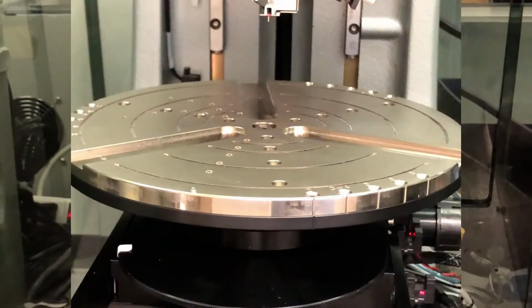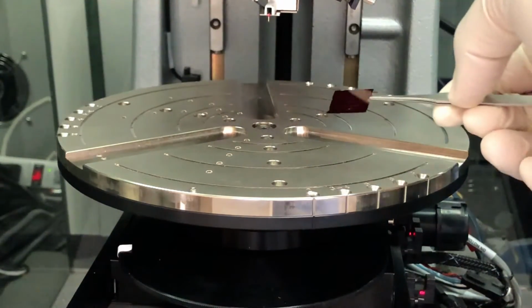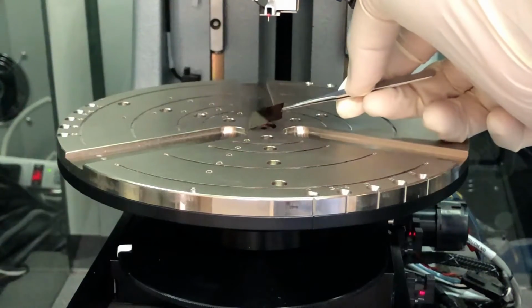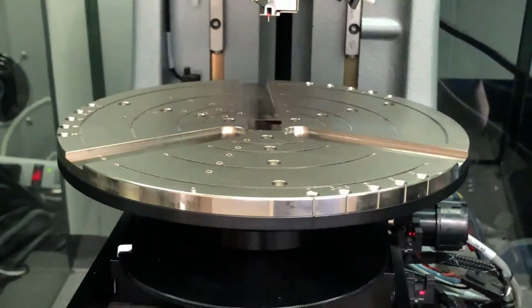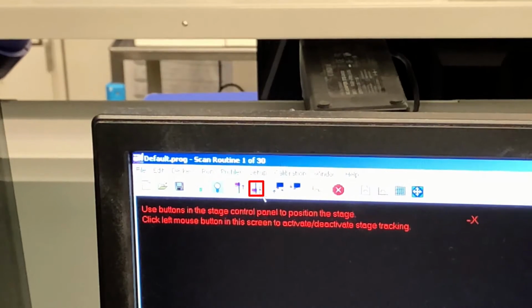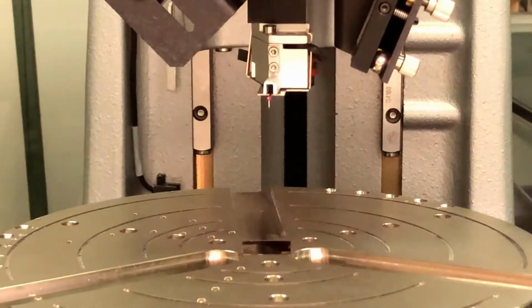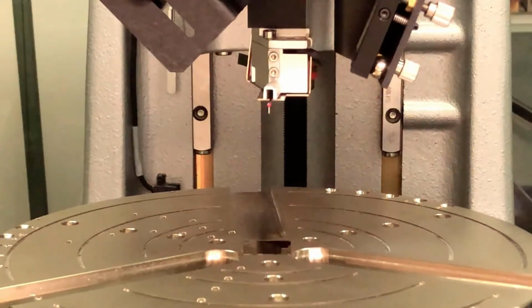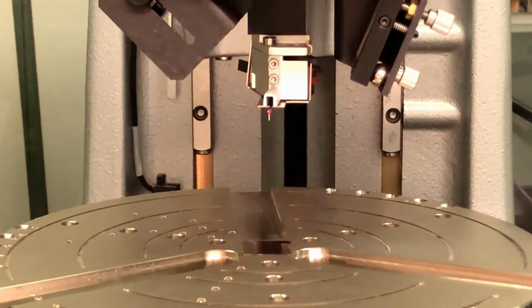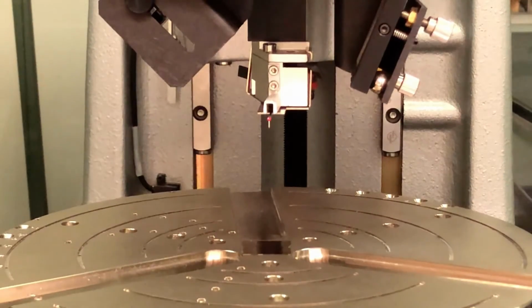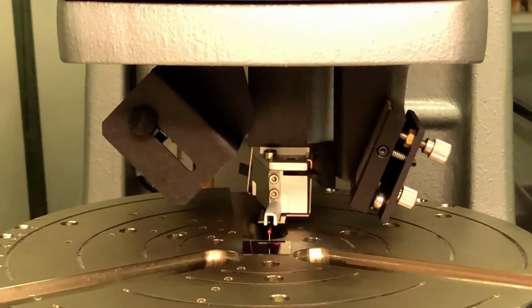Once it's in position, we can place our sample down so that it's underneath the probe tip. We can try to position it so that the scratches are underneath the tip. To bring the probe into position, just hit the tower down icon in the profilometry software. You'll see the probe tip start to descend towards the sample. As the tip makes its final approach, it will touch the surface and then retract.